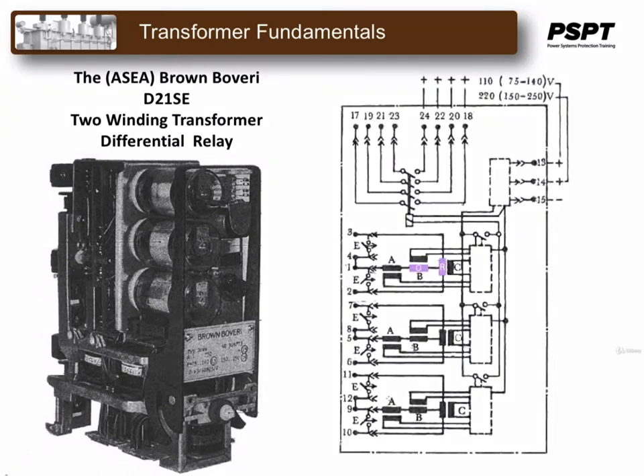I've highlighted here what would be considered the red phase operating and restraint coils for this relay, being fed with CT secondaries from the high side and the low side of the transformer. This shows the white phase operating and restraint coils being fed from the high side and the low side of the transformer, and this is the operating and restraint coils for the high voltage blue phase side of the transformer and the blue phase low voltage side of the transformer.